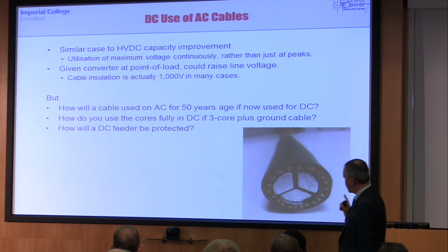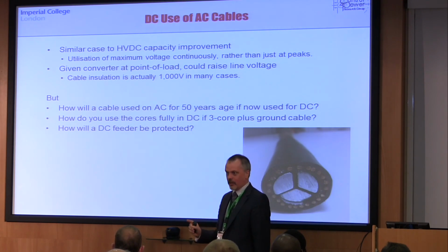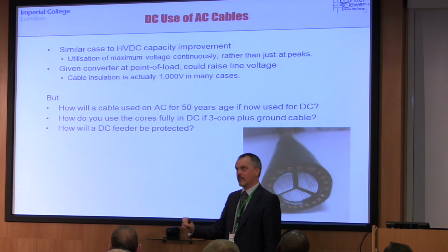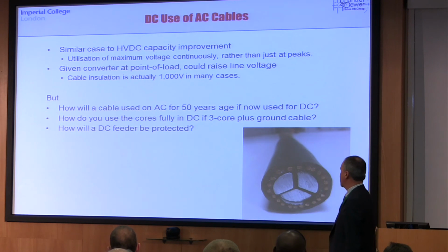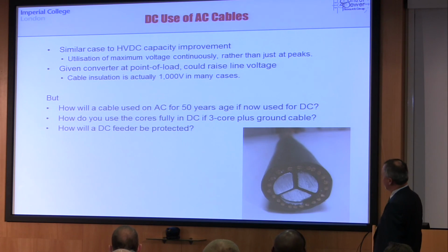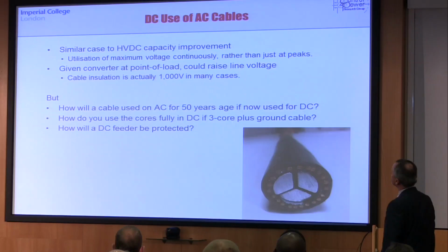A lot of people got interested in turning the final mile DC. If the point is to not rip the pavements up and use the same infrastructure but use it differently, then we've got a couple of questions to answer. Sorry, I should have said, first of all, we've got an opportunity. If we do that, we can probably exploit the fact that most of those cables actually have 1,000-volt insulation, not 400-volt insulation. And we can go up to the 1,000 volts and stay at the 1,000 volts of DC rather than just hitting that as an AC peak.